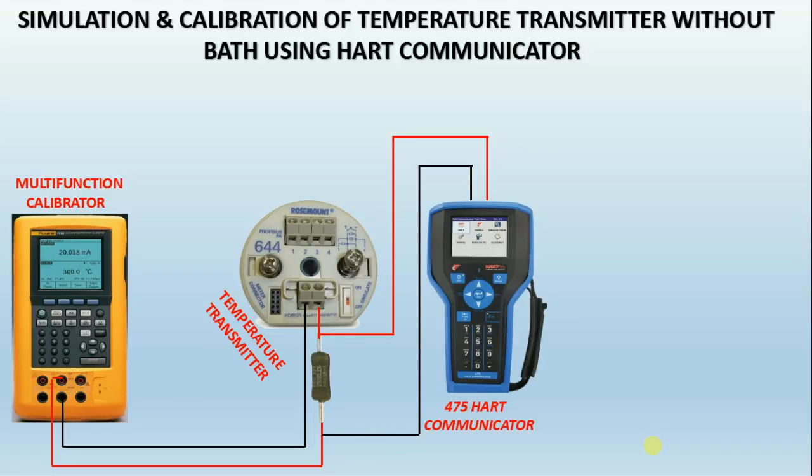Typically, temperature transmitters isolate, amplify, filter noise, linearize, and convert the input signal from the sensor, then transmit a standardized output signal to the control device. Common electrical output signals used in manufacturing plants are 4 to 20 milliamps. Now we will see how to simulate and calibrate a temperature transmitter using HART.